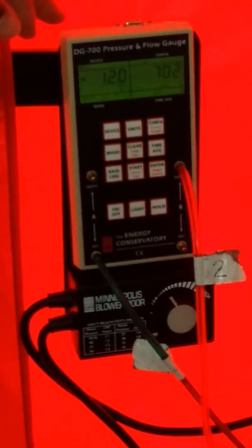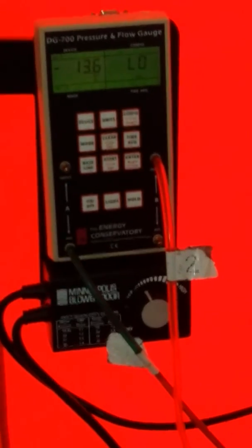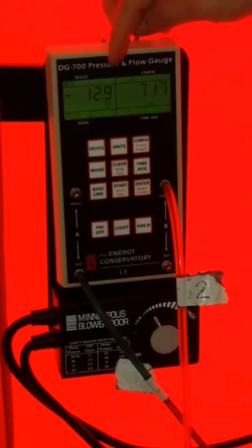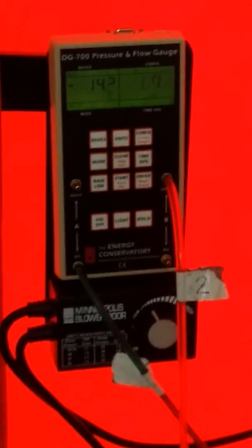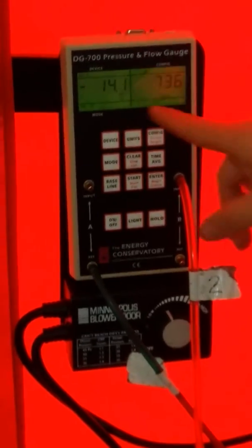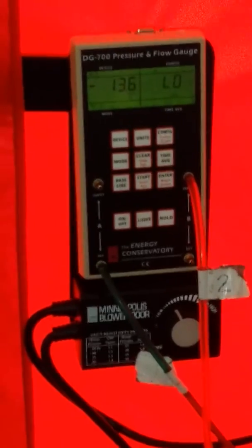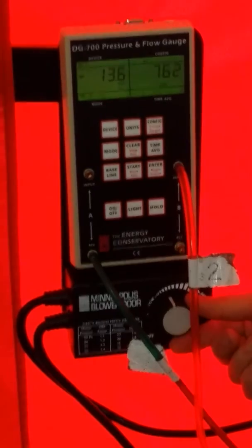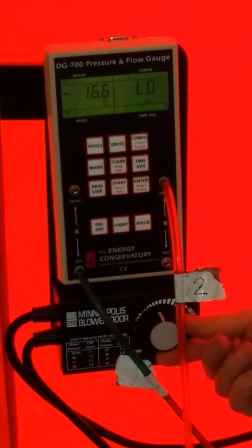Why do you say it's too low over here? We need to get to 50. What are we aiming for? Two point something? Well, then we're way beyond two point something. 50. Okay, are we at 50 yet? Ah, that's why we're too low, because our target on the left is going to be negative 50 pascals and we haven't reached it. So just keep increasing the fan speed. A little bit more. A little bit more.